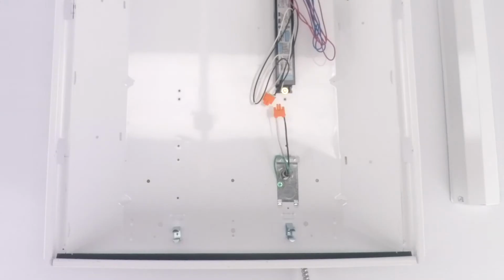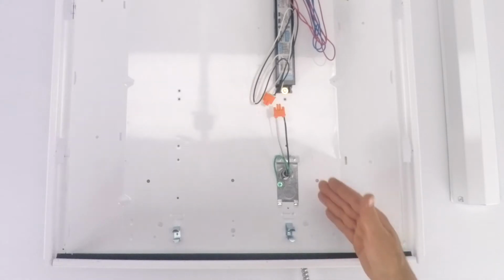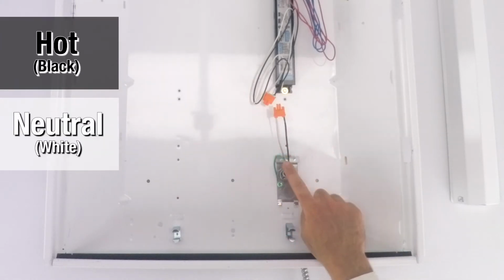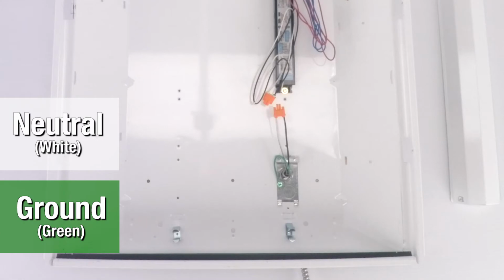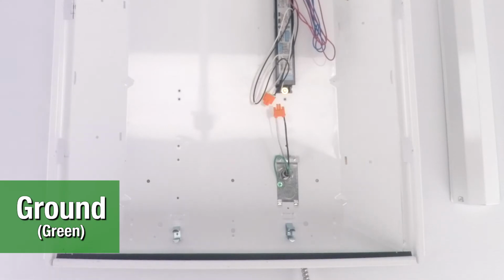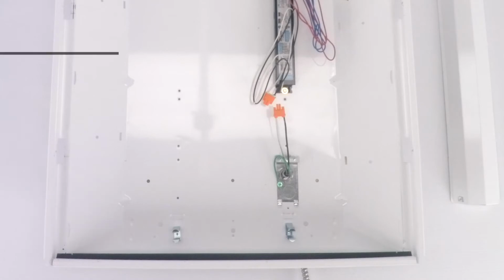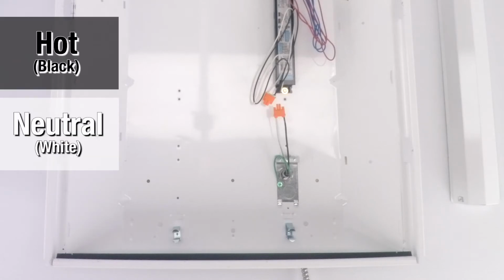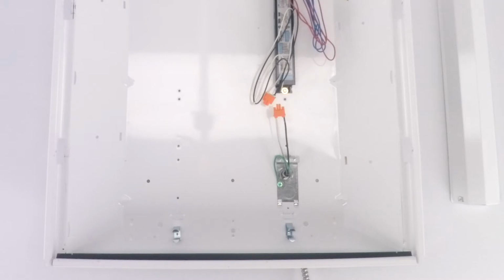So going through the fixture a little more, you can see coming into the fixture are three wires, a black, a white, and a green. The green one's ground. Green always goes to the light fixture to ground the fixture. You must have a green and it must be connected for safety. The black is hot and the white is neutral. In a few minutes, we're going to be looking at that a little closer.